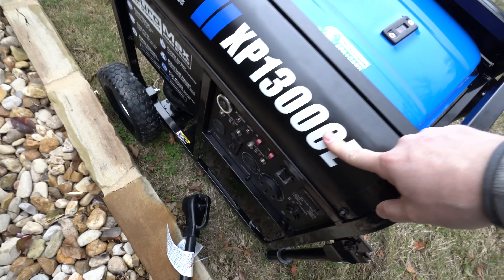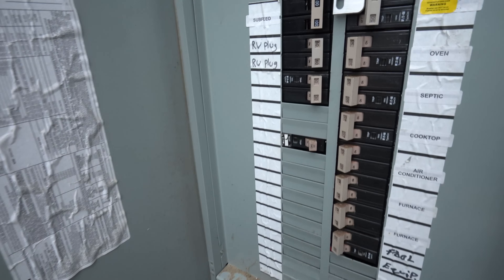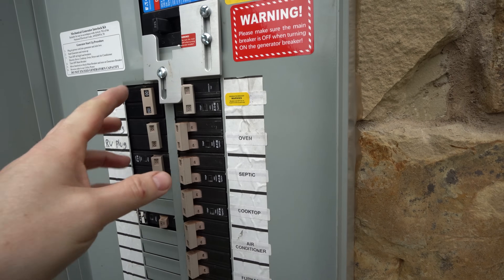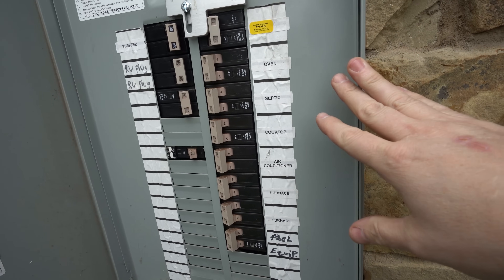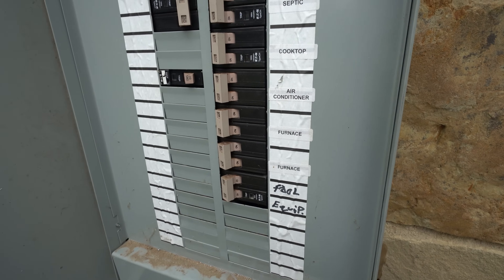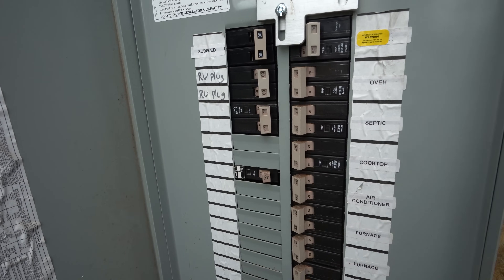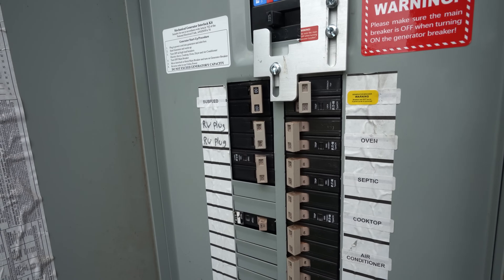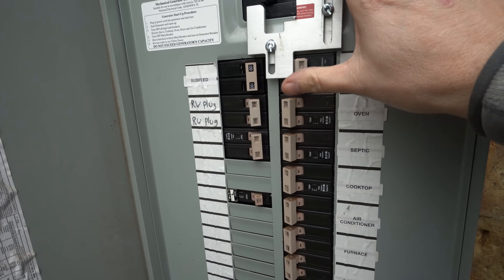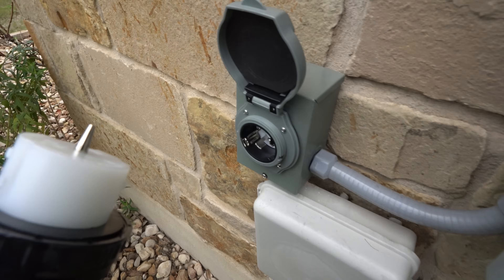Here's the full simulation. Assuming power is already out, come to the master panel, flip up and turn off the main, then turn the generator breaker on. At the same time, you'd flip off most circuits — leave on the pool pump, maybe the septic so it doesn't freeze, but turn off the cooktop, the RV sub-feed. We don't have enough capacity to run the furnace or air conditioner. Leave on the lighting and plug circuits.